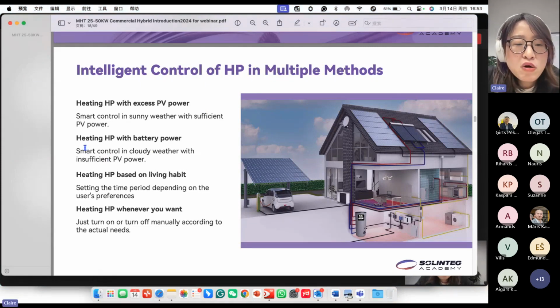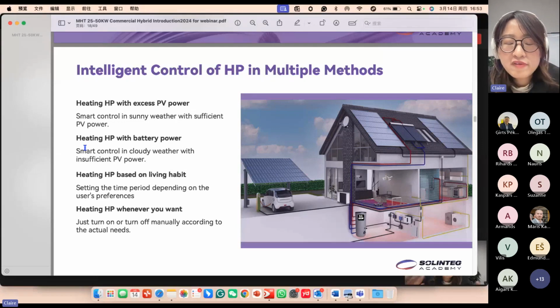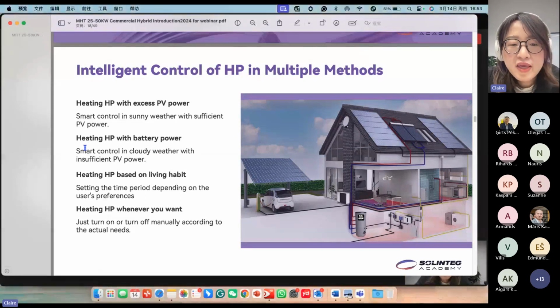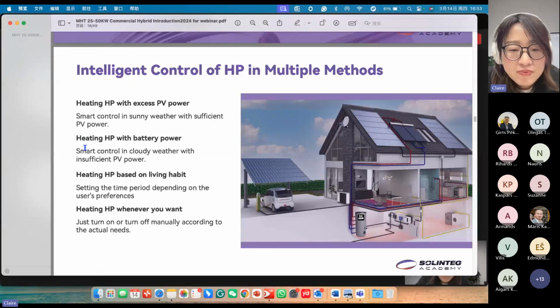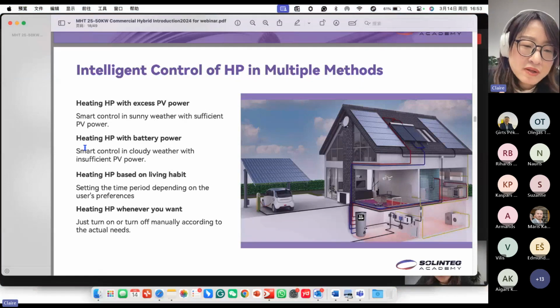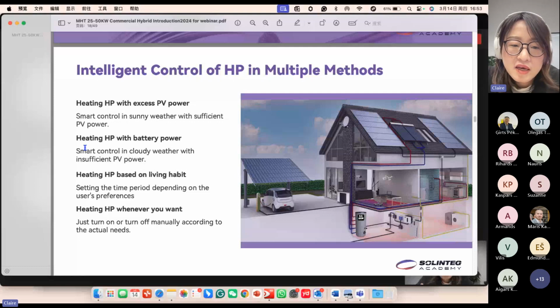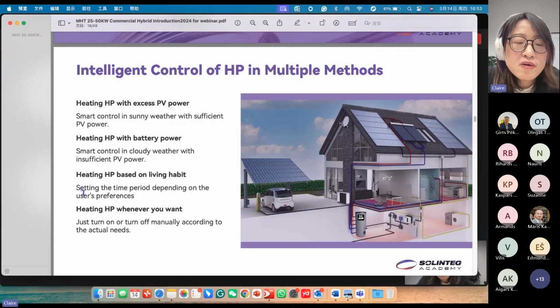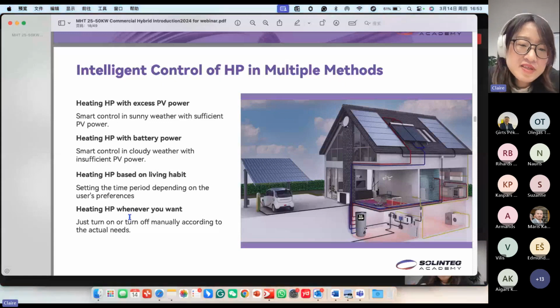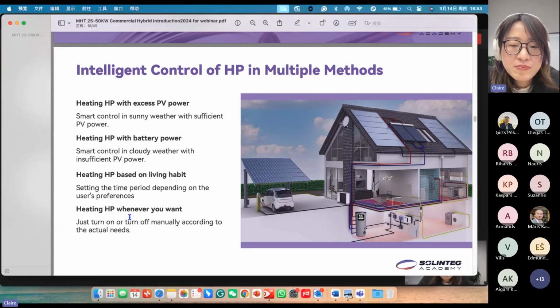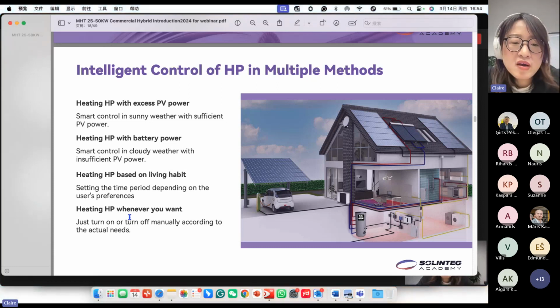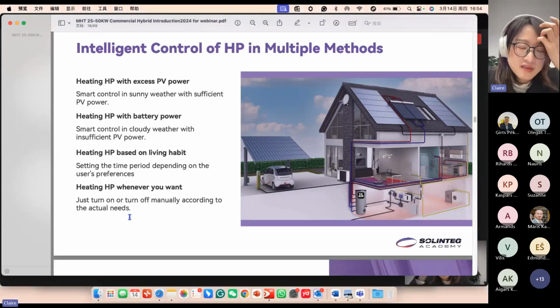And we can also control the heat pump according to the battery's SOC value. When the SOC value is at a high level, like 80%, we can use the battery power to activate the heat pump. And when the battery goes down to 40%, we can deactivate the heat pump. This value can be set on the application. We can also control the heat pump according to your lifestyle habits. For example, if you usually use hot water in the evening after work, you can preset the start time of the heat pump before you come back home. And you can also manually control the heat pump remotely by just clicking the on/off button on the application.